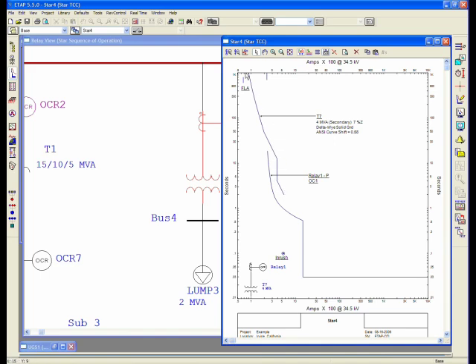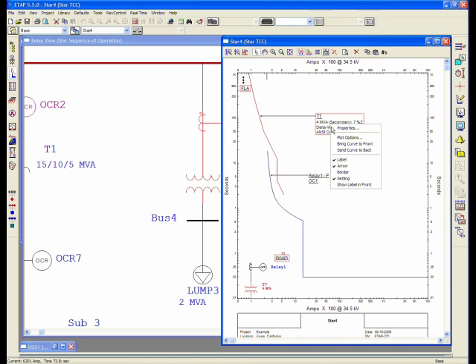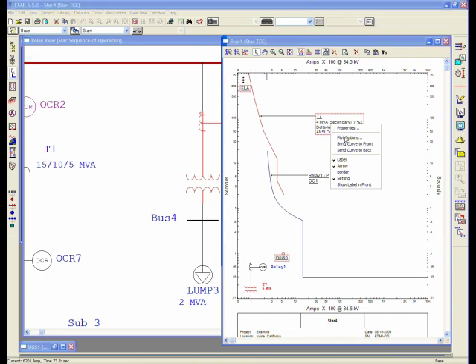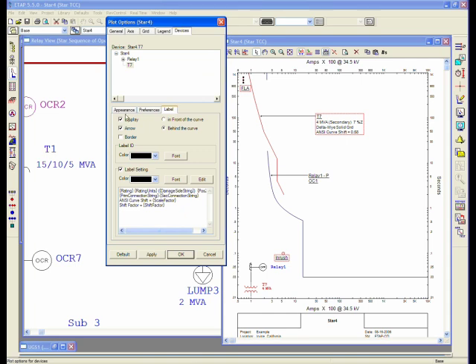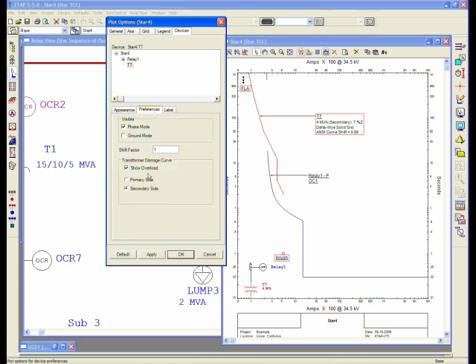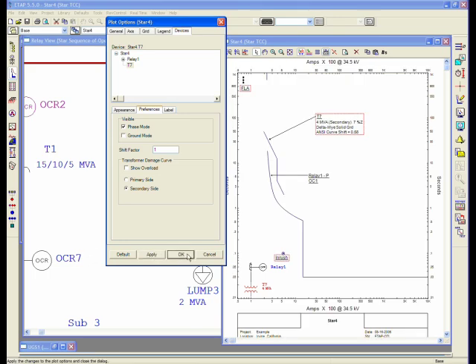The overload section is something that you might not typically show on your TCC, but you have the option of turning that off, which you would do by right-clicking here, and you would say plot option. You click select plot options, and you can go to the preference tabs and disable the show overload.